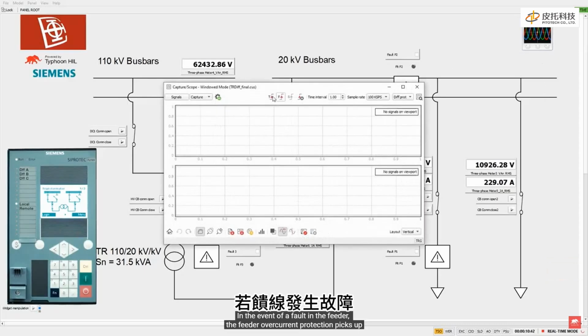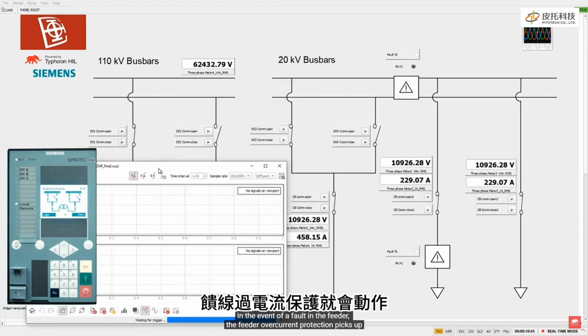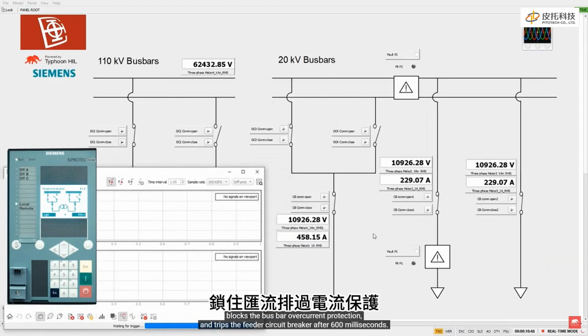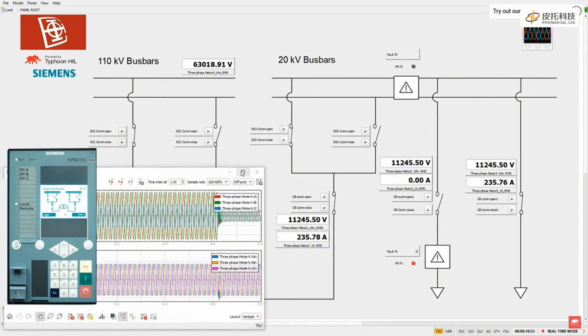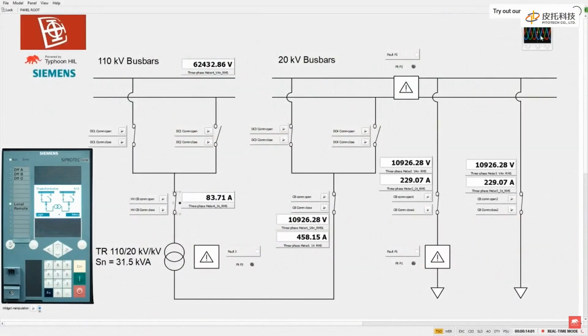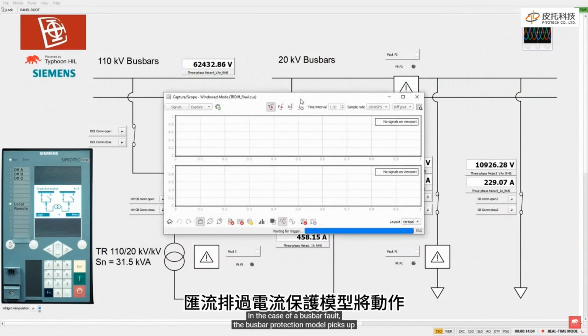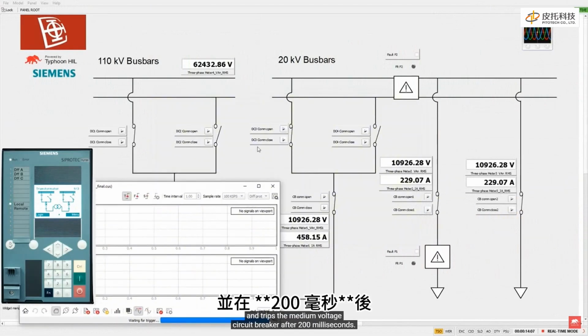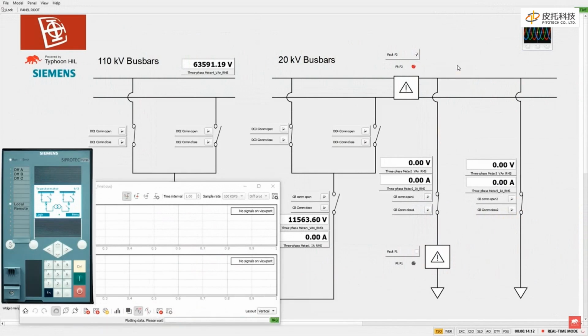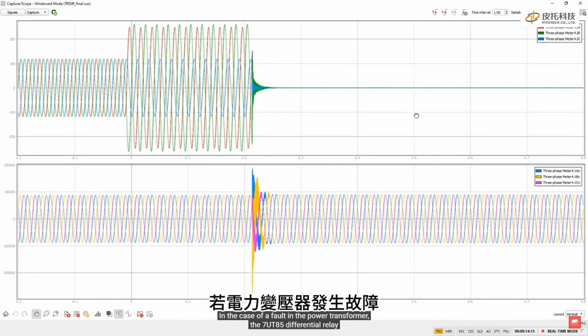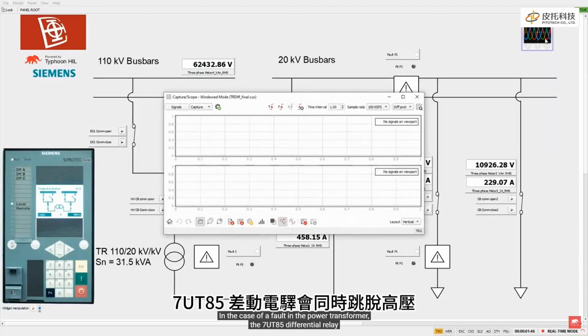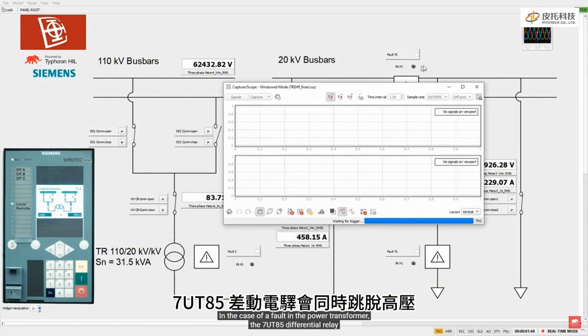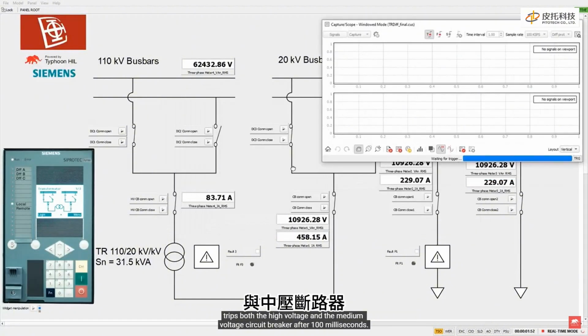In the event of a fault in the feeder, overcurrent protection picks up, blocks the busbar overcurrent protection, and trips the feeder circuit breaker after 600 milliseconds. In the case of a busbar fault, the busbar overcurrent protection model picks up and trips the medium voltage circuit breaker after 200 milliseconds. In the case of a fault in the power transformer, the 7UT85 differential relay trips both the high voltage and the medium voltage circuit breaker after 100 milliseconds.